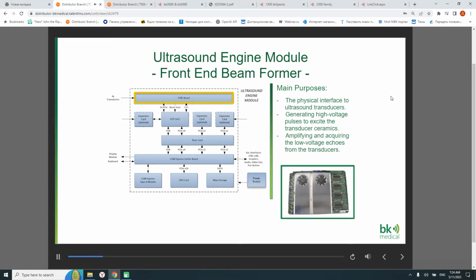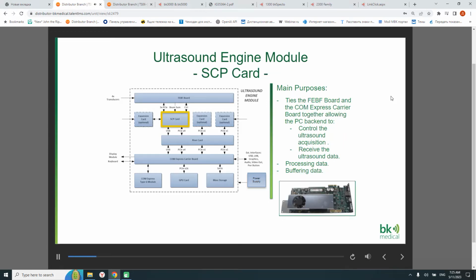The front-end beamformer board's main purpose is that it's a physical interface to the ultrasound transducers. This is where we're generating our high voltage pulses to excite the transducer ceramics. And it's also where we're amplifying and acquiring the low voltage echoes from the transducers. The SCP board's main purpose is that it ties the front-end beamformer board and the COM Express carrier board together, allowing the PC backend to control the ultrasound acquisition and receive the ultrasound data. This is where we also do processing of data, and we are buffering data as well.